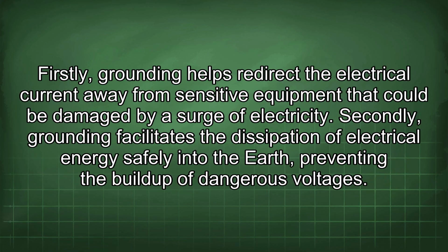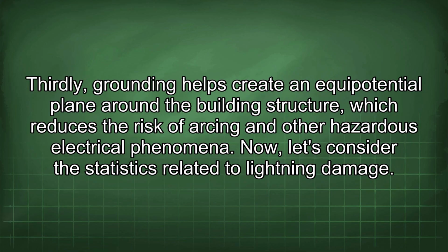Firstly, grounding helps redirect the electrical current away from sensitive equipment that could be damaged by a surge of electricity. Secondly, grounding facilitates the dissipation of electrical energy safely into the Earth, preventing the buildup of dangerous voltages. Thirdly, grounding helps create an equipotential plane around the building structure, which reduces the risk of arcing and other hazardous electrical phenomena. Now, let's consider the statistics related to lightning damage.